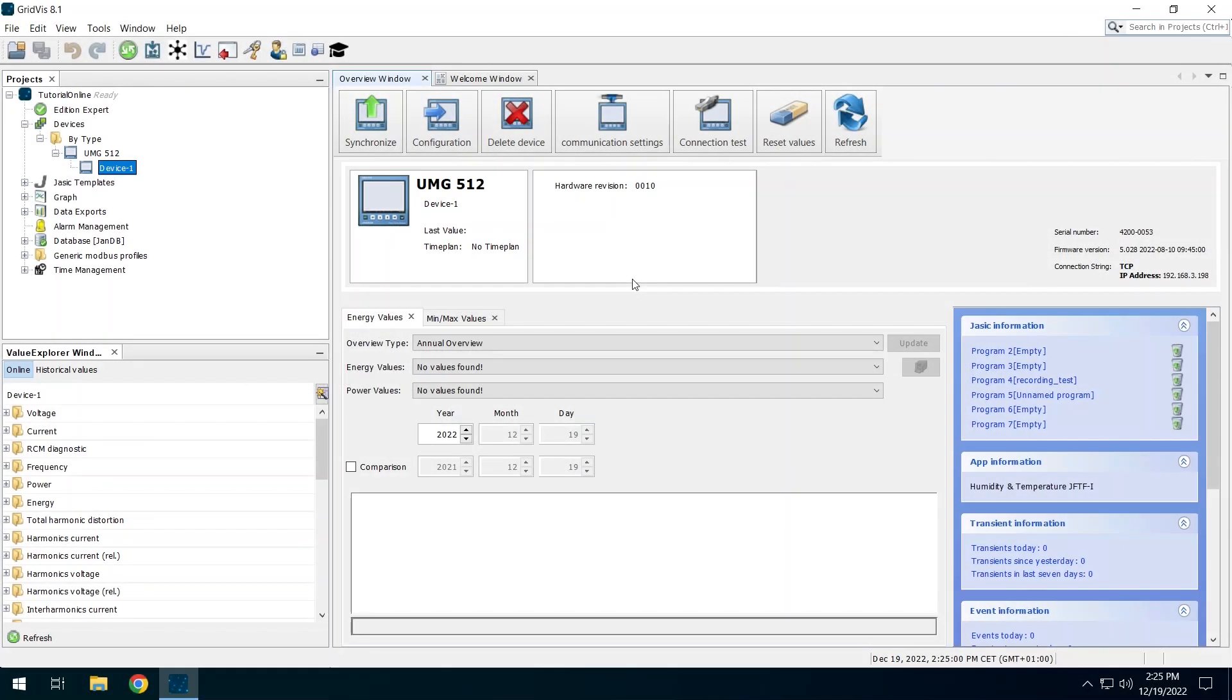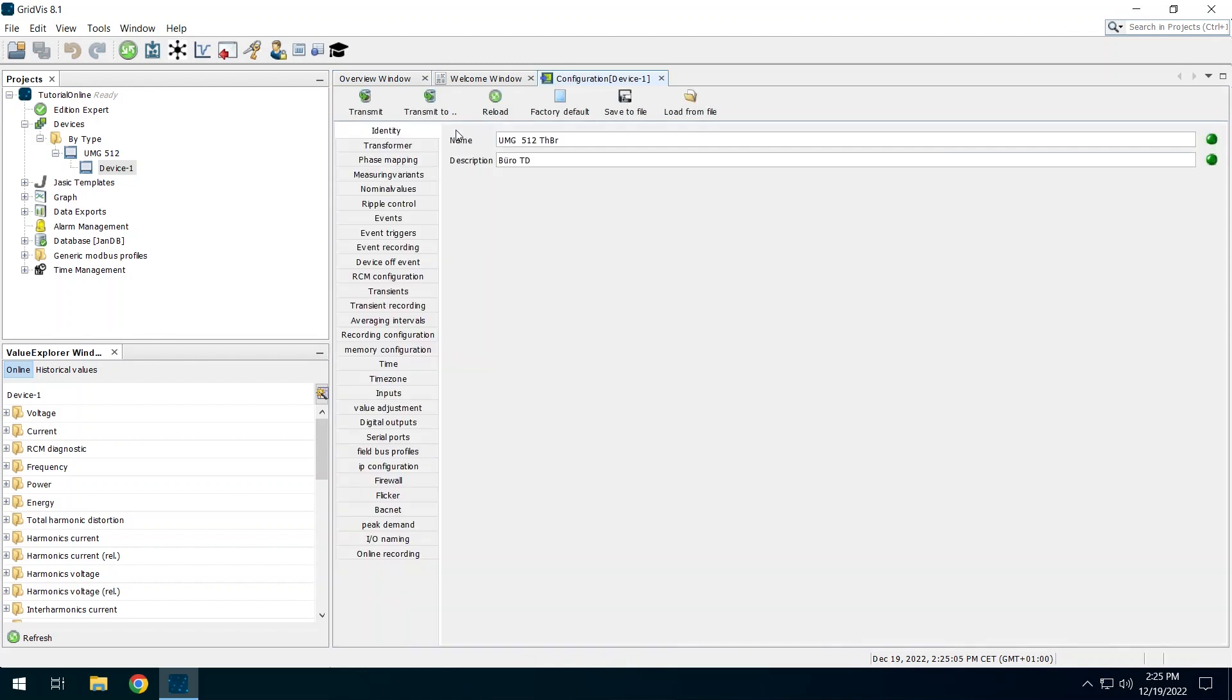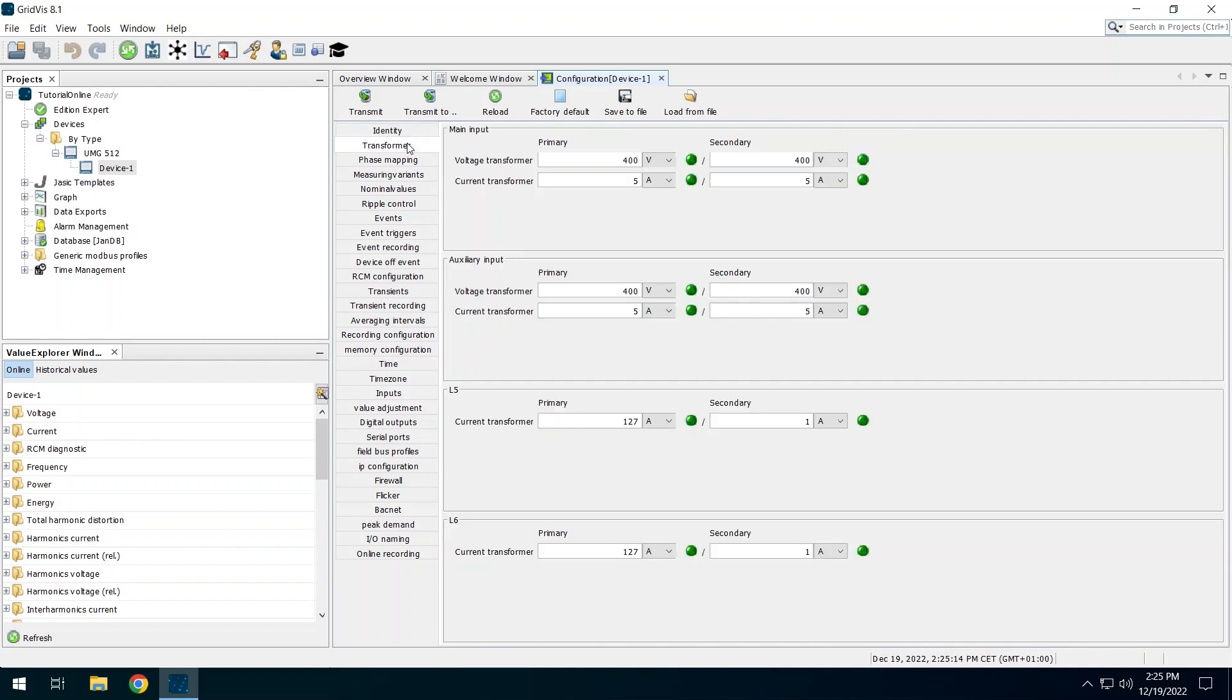Open the configuration. The interface of the device configuration differs depending on the device. Go to the entry of the current transformers. Set the transformer ratio of the connected transformer. In this example it is a 100 to 1 transformer.